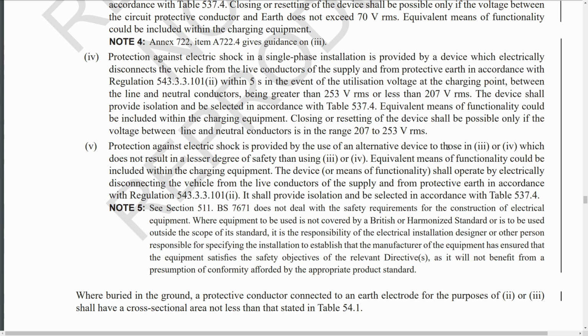Now, if you have a three-phase supply to your particular property, so more in the commercial or industrial environment, then a device that does this is valid in pretty much all circumstances, because the difference there is you can actually monitor the voltage on all three of the phases and the neutral conductor coming in. So therefore, if the voltage goes outside that range on any one of the phases relative to neutral, then it will disconnect all of the phases, the neutral and the protective conductor, and of course that's absolutely fine. But say with a single phase installation, of course, you've only got access to one phase, and if you're unlucky enough to get the one which is remaining within that range relative to the neutral, then of course it's not going to disconnect, even though that could be a dangerous situation.